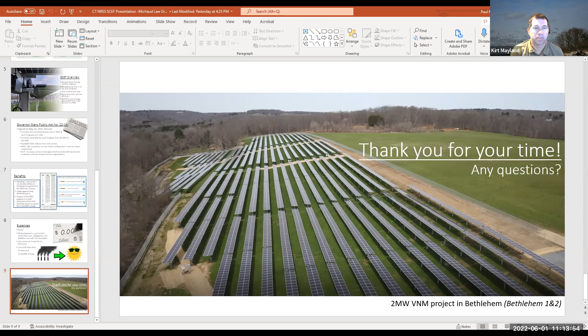So my understanding, and I've done this a few times in floodplains, actually in a brownfield in a floodplain, the primary concern is not that the river will spill over the banks and there'll be 2 feet of water up to nearly the lower edge of the panel. The primary concern is that water will get into the underground conduit, and somehow make its way back up into important infrastructure like the inverter and transformer. So as long as it's well constructed, the conduit is sealed, and you have the right electrical installers, for the most part, building in a floodplain, taking away the environmental sensitivities from a construction standpoint, is possible.